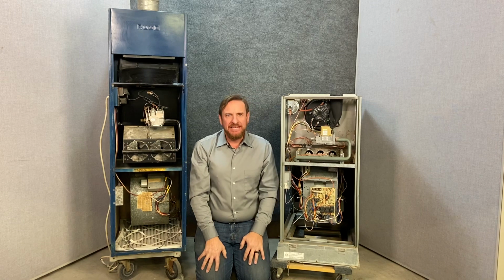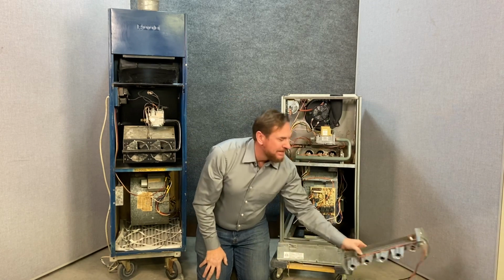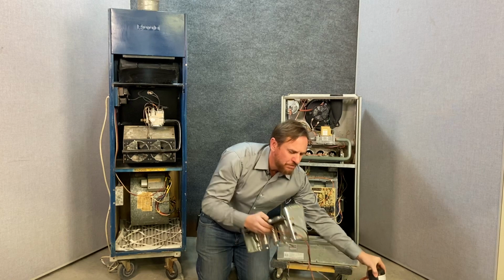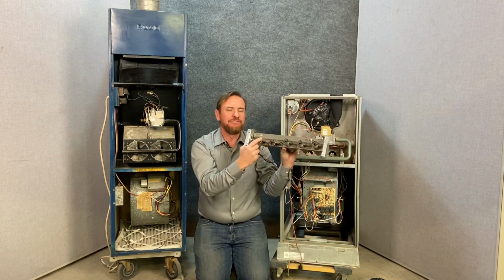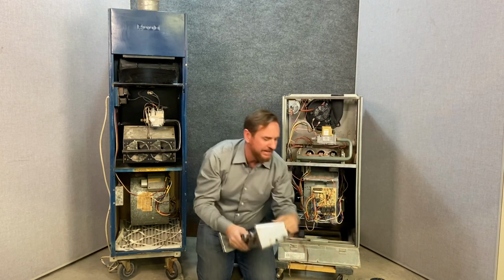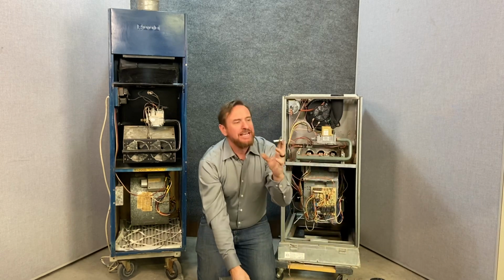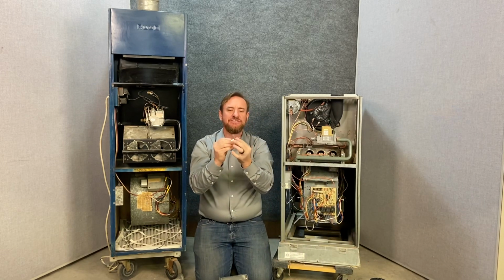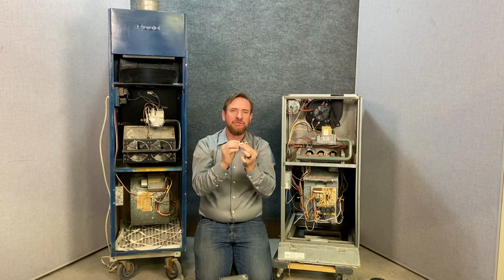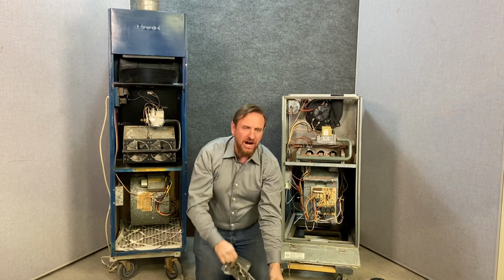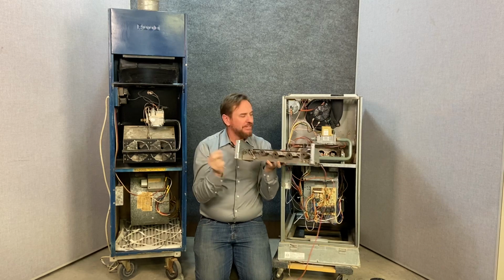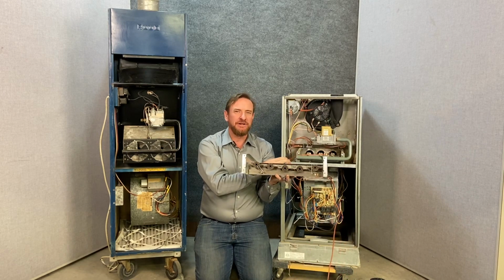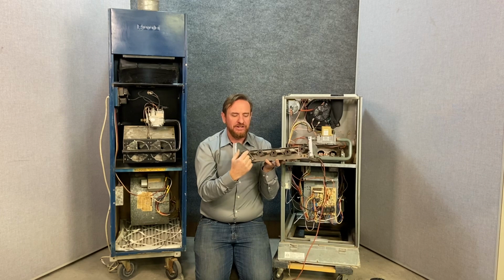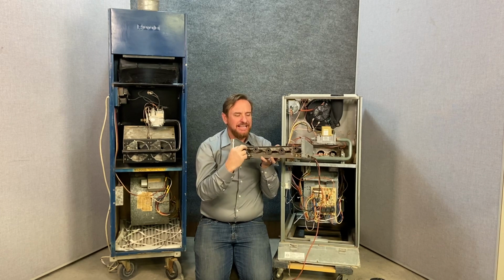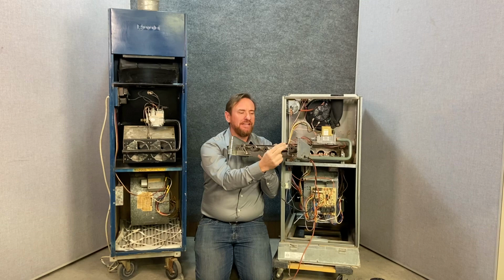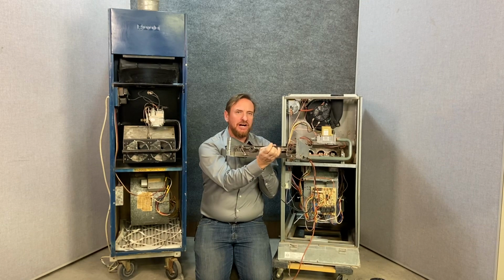Now let's talk about safety after it fires up. This system has a flame sensor, which is a single rod that's going to be in front of the burners. That single rod is what's going to sense a flame. And it looks something like this. We'll get into the details of how this works in another video, but it's just a single rod flame sensor. And it's actually on the opposite side of where it ignites. So this particular model is a direct spark ignition, DSI. It makes an arc, and it lights the gas, and then it has to go all the way across all the flames before it senses a flame on the opposite side.